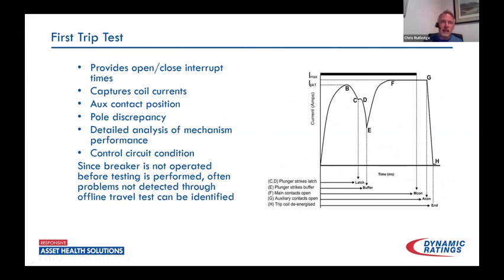We can overlay test signatures and compare them. If the test is still looking good, we're probably still good on all timing and travel characteristics. The first trip test was something I incorporated. We would bypass the breaker being tested, either through a reserve bus or bypass switches, and run this test before the breaker is operated and at a time when it hasn't recently operated. Due to the nature of the grease in the breaker, as it sits for long periods of time, the thickener and lubrication components tend to separate. That first trip can be ten times longer than the rated time for the breaker. But with actuation, you remix those components and your next test would be fine.